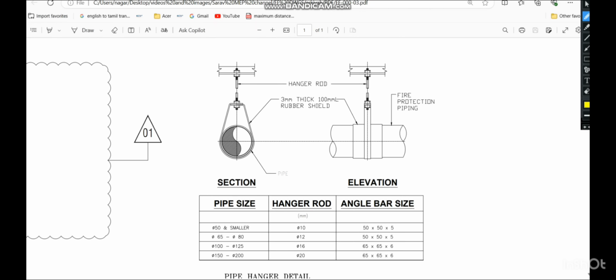And in this image you can see different pipe sizes and hanger rods. So here I have shown a hanger rod support. For diameter 50 and smaller, a 10 mm hanger rod we need. For 65 to 80 it is 12 mm, 100 to 125 it is 16 mm, 150 to 200 it is 20 mm. So this type of hanger rod we have to provide. Additionally, we have given the angle bar size also. So different angle bar sizes we have to provide for the firefighting system. This is for the pipe.